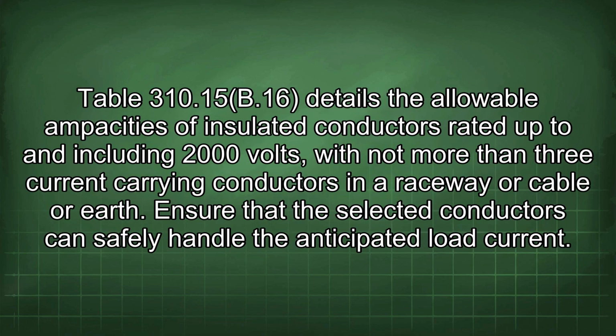Table 310.15(B)(16) details the allowable ampacities of insulated conductors rated up to and including 2000 volts, with not more than 3 current-carrying conductors in a raceway or cable or earth. Ensure that the selected conductors can safely handle the anticipated load current.